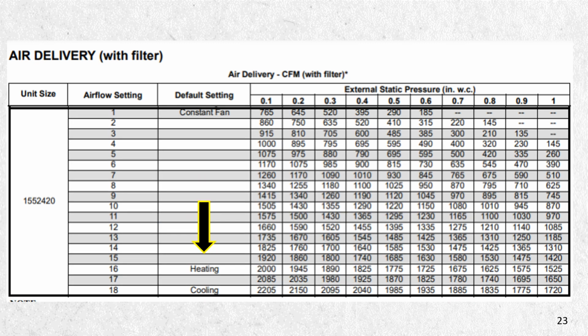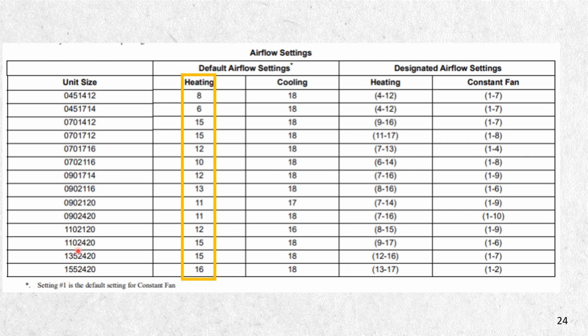So this is another model, has the same kind of 2000 reading here, but you can get 2200 if you're really close to zero resistance. You're going to be right in this. This is where they want you, around that 1985 to 2000 range, and you can see why they say that range. So these are the models here, and these are your factory settings in heat, factory in cooling. And these are your options in heating. I can go from speed 13 to 17, but in my constant fan here, I can just go between 1 and 2. So make sure you're looking at this and make sure you understand what my factory setting is. So let's say you're not hooking it to a cell phone, or you're not using it to program with your cell phone. You're going to be able to run it, and it's going to come on at these factory settings.